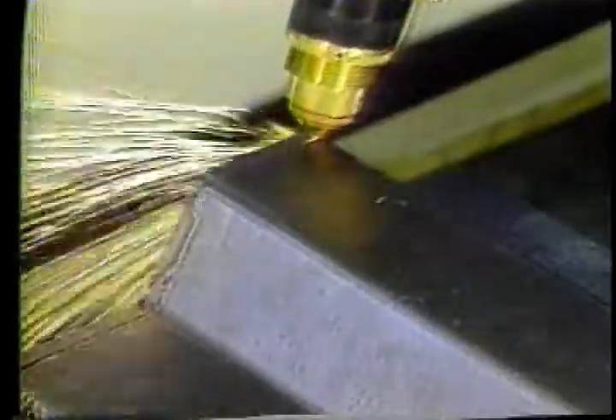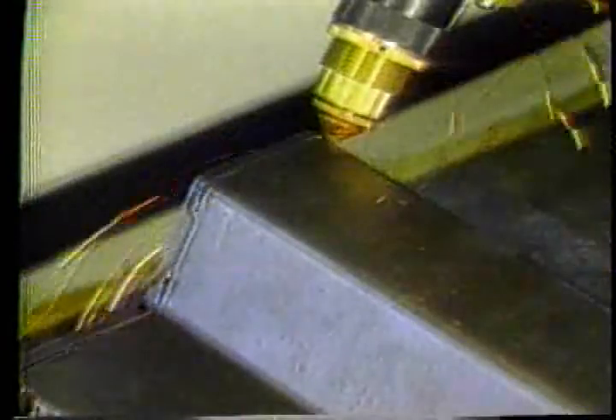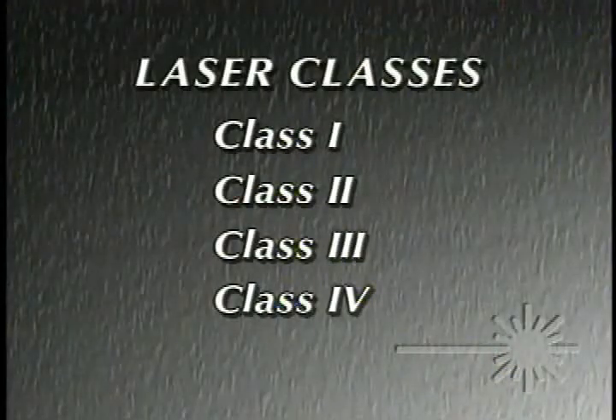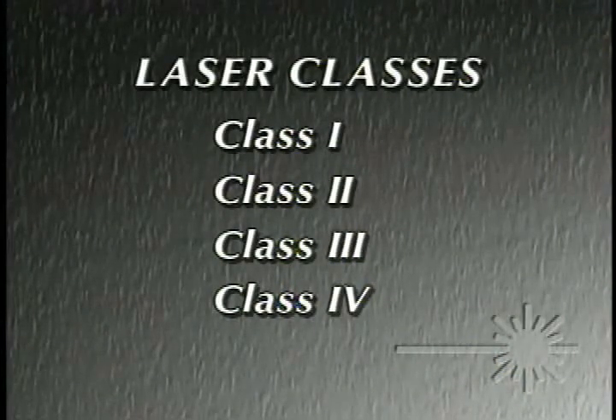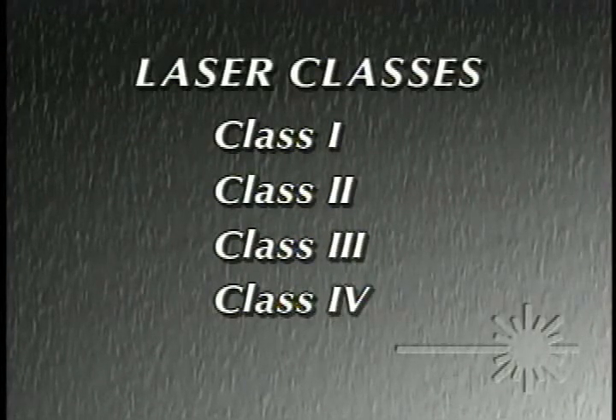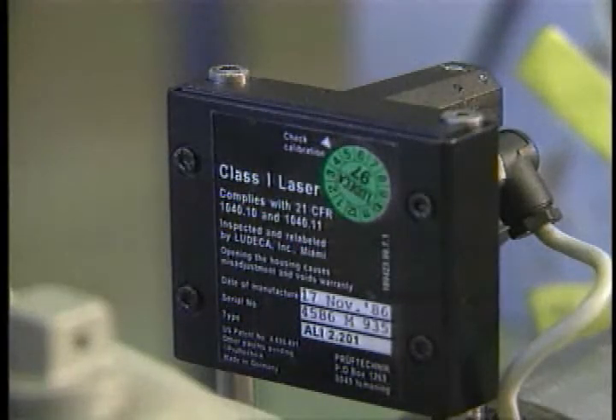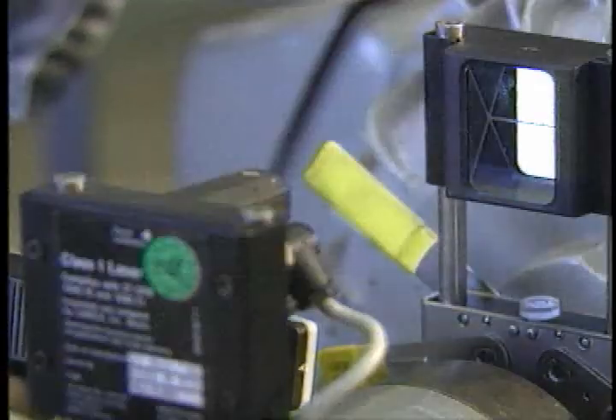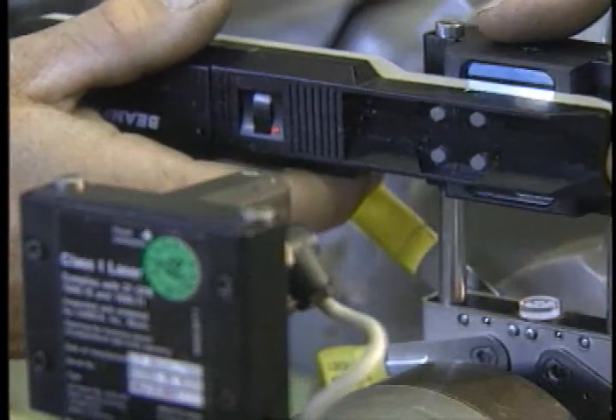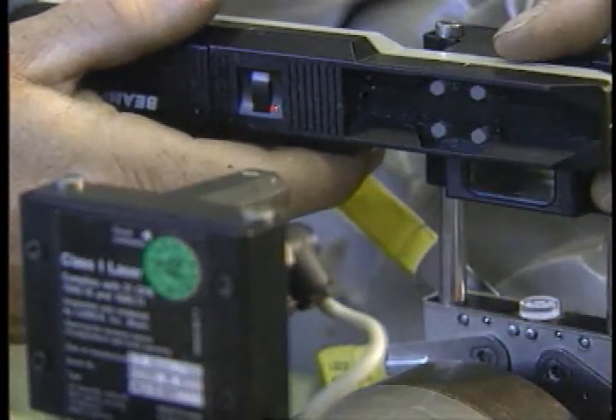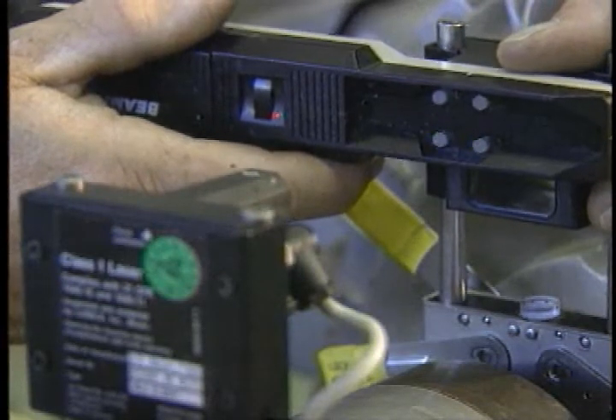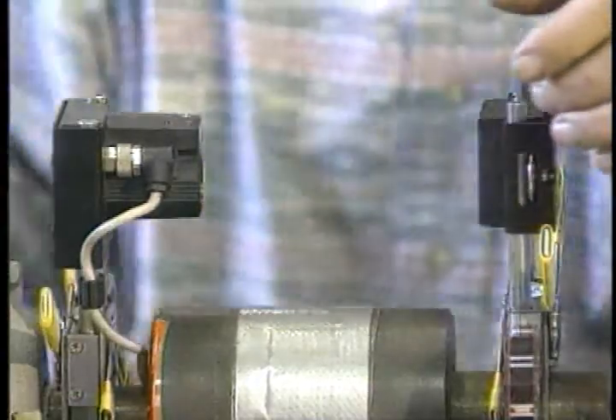The precautions to be taken depend upon the class of the laser being used. There are 4 classes of lasers, which are designated simply Class 1, Class 2, Class 3, and Class 4. Only Class 1 and Class 2 lasers are used for shaft alignment. Class 1 lasers produce no known hazard to humans. They emit a low-power beam, which may be either visible or invisible. Class 1 lasers have been the traditional choice for alignment equipment, but some newer models are now using Class 2 lasers.